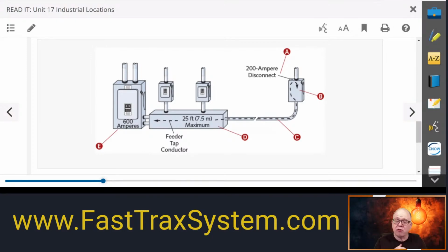It could be the load side of the lug. So you could have, this is your breaker, this is right here, and this is a feeder. But maybe there's a set of lugs here that's being run all the way to this piece of equipment, and the 25-foot rule would apply all the way to here. So it could happen to a conductor in here, or it could happen on the load side of a breaker in here, on the load side of a main breaker, for example. Because the whole rule is this conductor is not sized based on this protection. So that's why we're utilizing the tap rules.